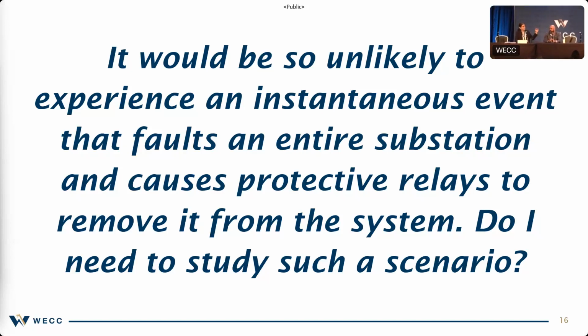Even a plane going into a substation and taking out a variety of elements, there will be at least microseconds, or maybe even full seconds, as things are taken out. One of the things that came up during the last round of CIP 14 comment period was the three-phase bolted fault—essentially saying I've got a three-phase line and I apply a simultaneous fault against my largest incoming line. Some comments from that last draft were that this is an unreasonable expectation, unlikely to occur. A counter argument is that we'd want to study the worst case to determine the worst thing that could possibly happen.